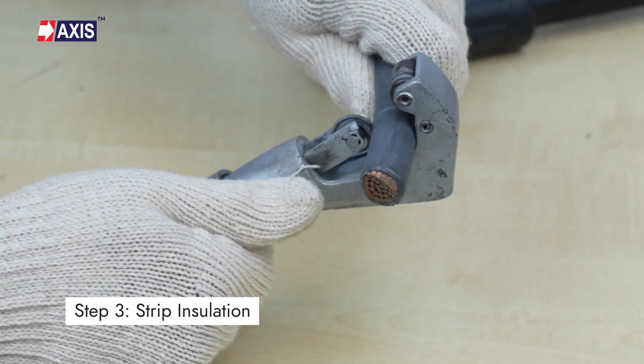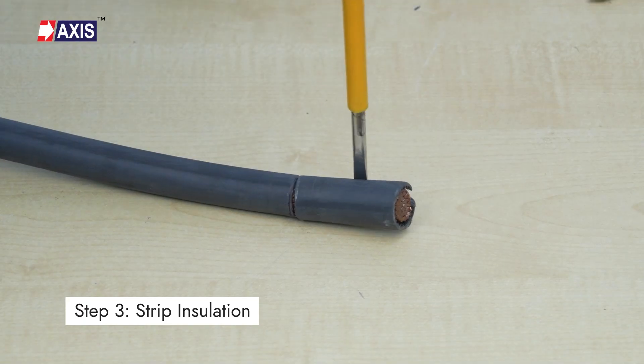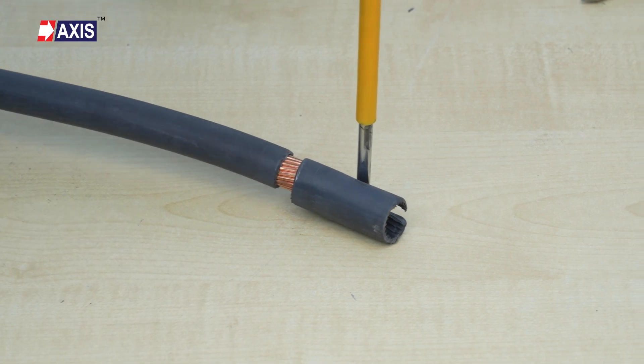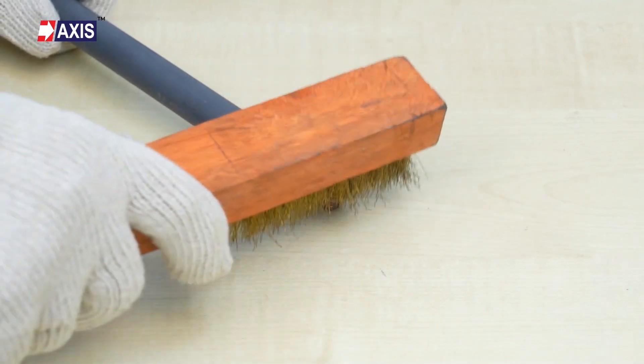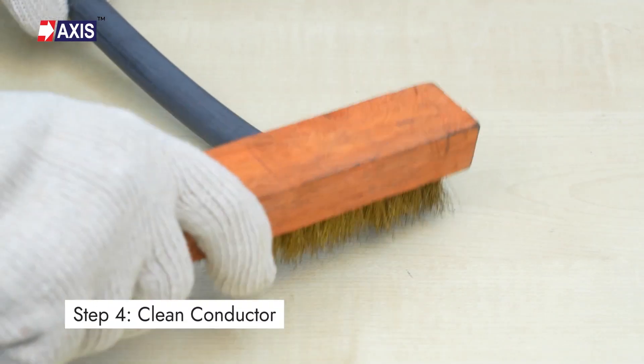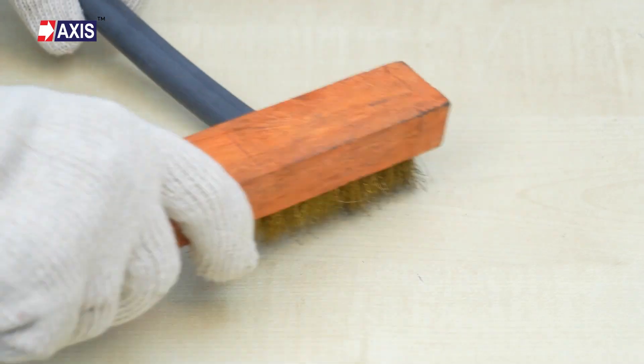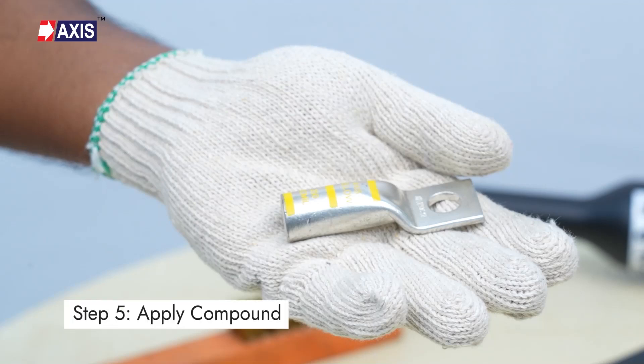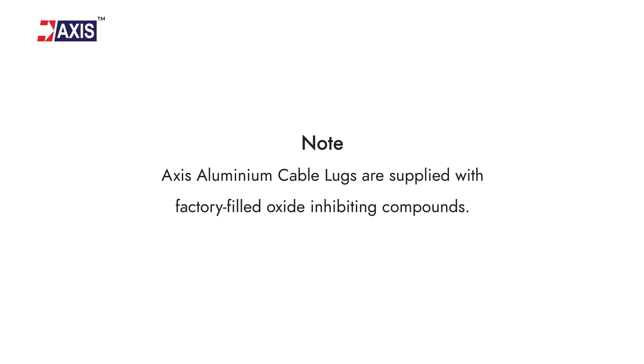Step 3: using a suitable stripper, cut and remove the cable insulation, leaving sufficient extra allowances of 3 mm to 5 mm. Step 4: clean or brush the surface of the conductor using a wire brush to remove any kind of oxidation. Step 5: apply oxide inhibiting compound recommended for aluminium on the cable strands. Note: AXIS aluminium cable lugs are supplied with factory filled oxide inhibiting compounds.